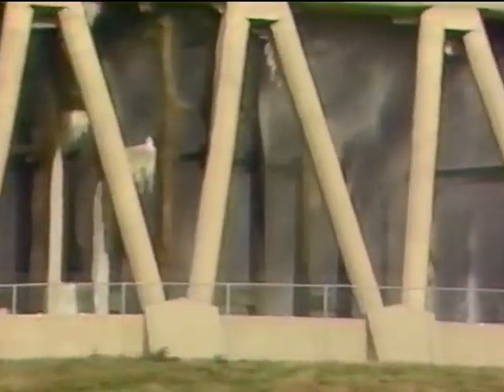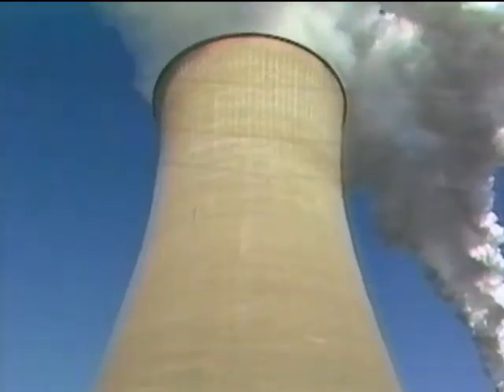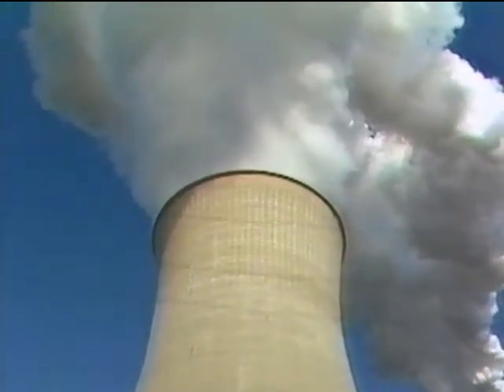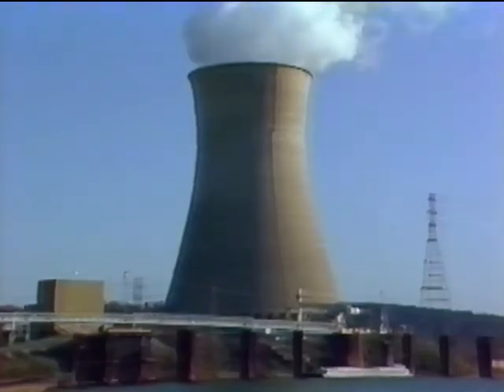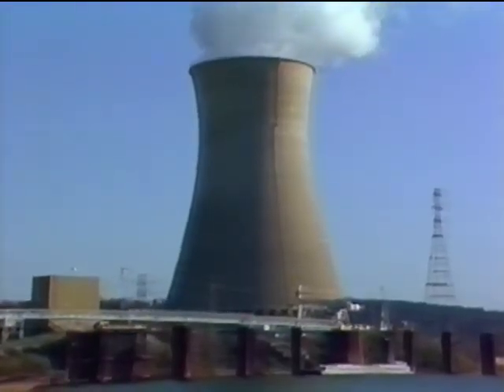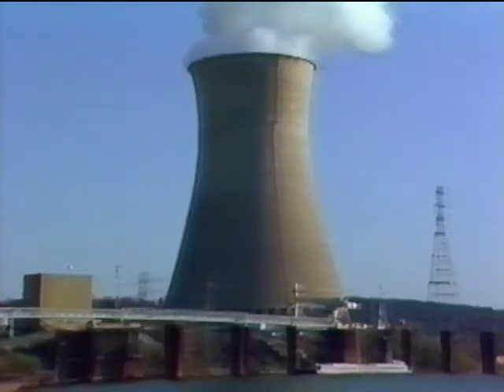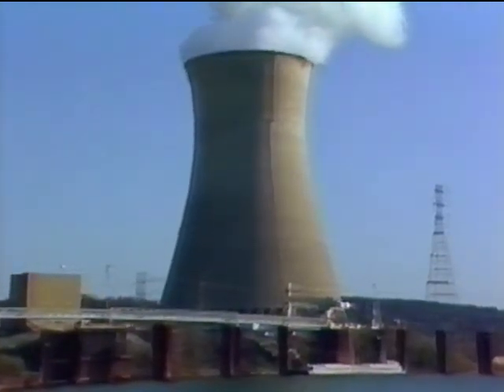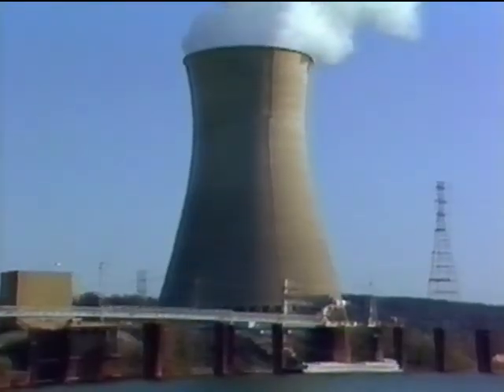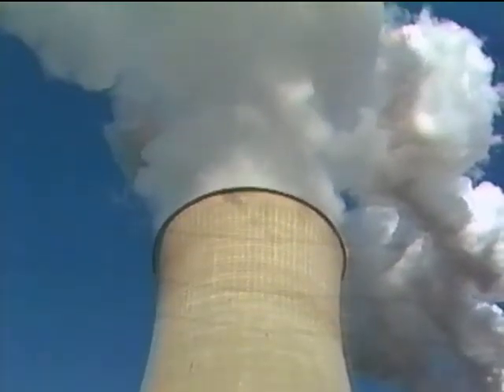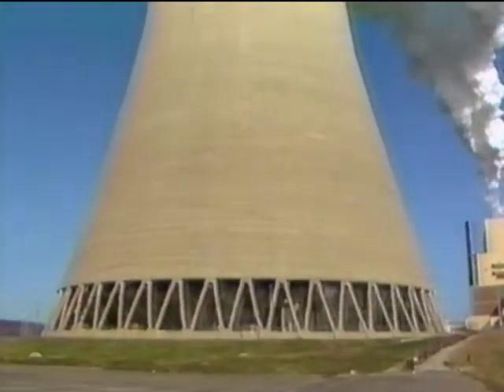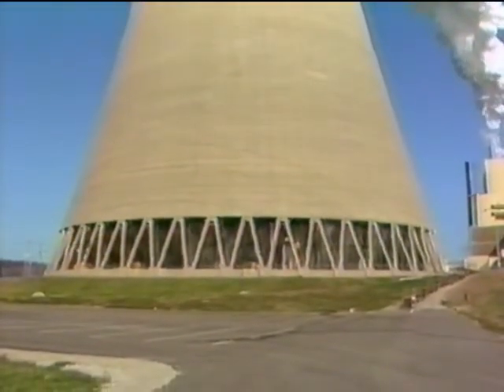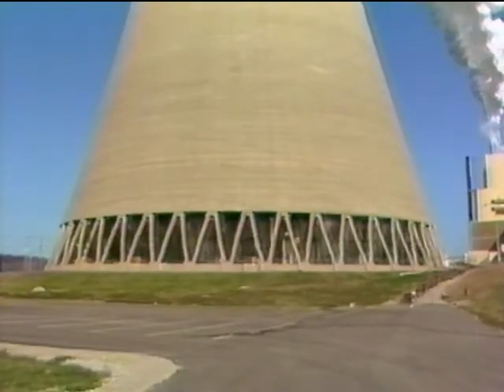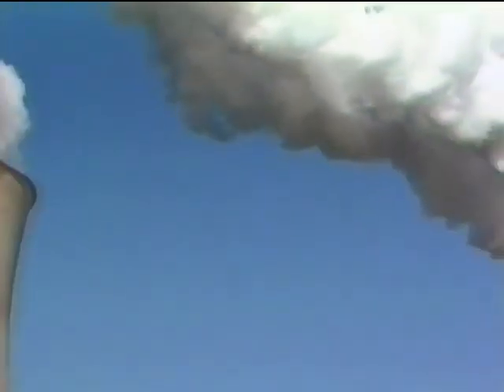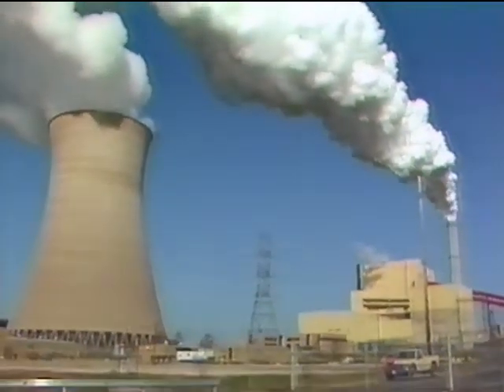by evaporation. Over 8,000 gallons of water is evaporated out of the top of the tower each minute. This water is replaced by drawing fresh water from the Ohio River. The cooling tower, which is just the right size to fit inside the playing field of Riverfront Stadium, is actually an environmental protection device. The unique shape creates a natural draft where the hot air rises faster, drawing more cool air in the bottom. The tower uses no electricity to cool the water. This evaporation process allows the plant to reject its heat to the air, not to the river, where the warmer water could affect fish and plants.